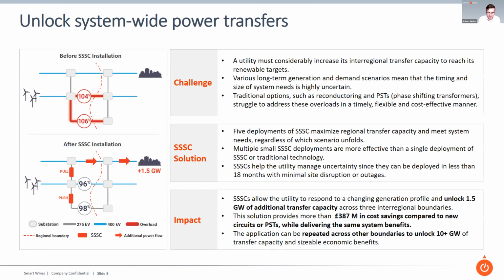The solution here found that using multiple small installations was more effective than one large installation in one location, as there were challenges with siting, cost, and the length of outages to do those types of deployments, whereas multiple small deployments reduce the length of outages, and the fast delivery of the SSSCs themselves compared to the PSTs and the reconductoring reduces the disruption to the grid as well.